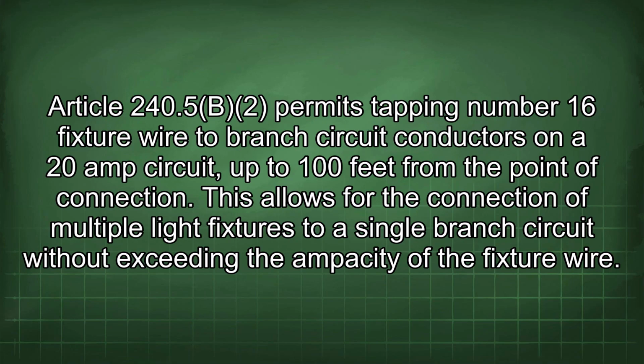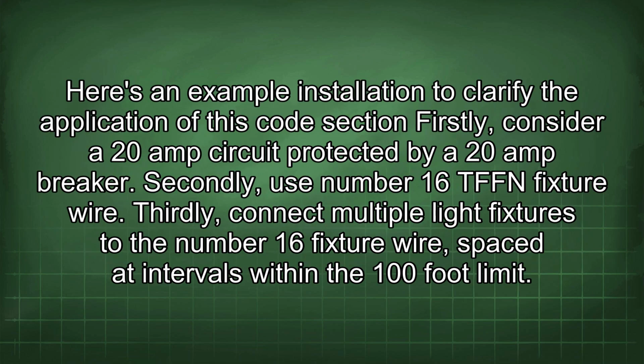240.5(B)(2) permits tapping number 16 fixture wire to branch circuit conductors on a 20-amp circuit up to 100 feet from the point of connection. This allows for the connection of multiple light fixtures to a single branch circuit without exceeding the ampacity of the fixture wire. Here's an example installation to clarify the application of this code section.